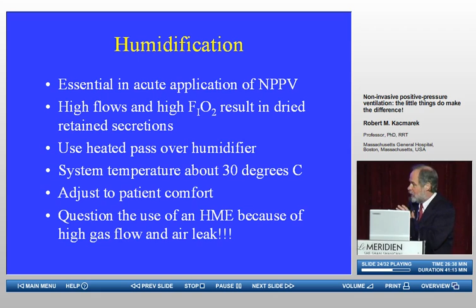Remember, every one of these has a limit to the volume that it can humidify. Most say that 700 to 1 liter is the optimal volume for humidifying the gas to whatever the defined humidity level, which in most is around a water vapor content of about 30 milligrams per liter. So you can get away with it in some patients, but I would be very cautious with the use of a heat and moisture exchanger. My own bias is to use an active humidifier in these patients.